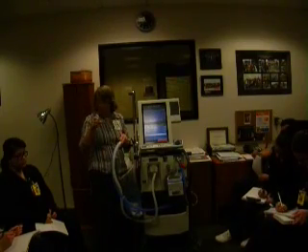Again. Now it's doing compliance. Compliance is testing for how compliant our circuit is. Does it let the air through easily or not? Some circuits, the plastic is more compliant than others. So that's what it's testing for on this one. Now it says block Y again, so I did, and I hit accept.